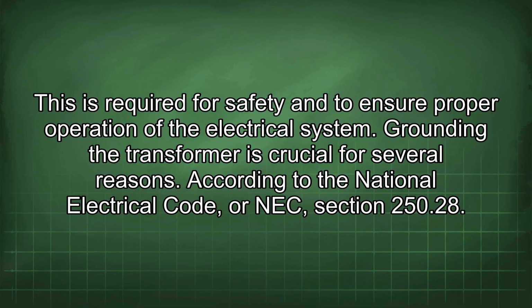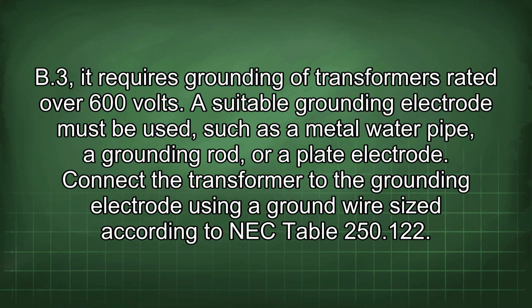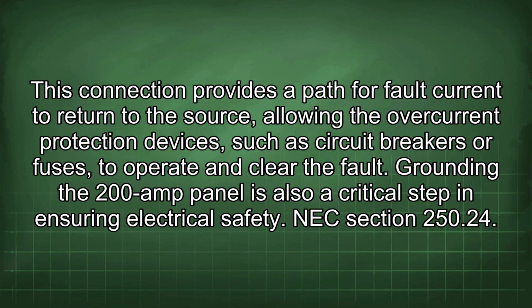Grounding the transformer is crucial for several reasons. According to the National Electrical Code, or NEC, section 250.28 B3, it requires grounding of transformers rated over 600 volts. A suitable grounding electrode must be used, such as a metal water pipe, a grounding rod, or a plate electrode. Connect the transformer to the grounding electrode using a ground wire sized according to NEC Table 250.122. This connection provides a path for fault current to return to the source, allowing the overcurrent protection devices, such as circuit breakers or fuses, to operate and clear the fault.